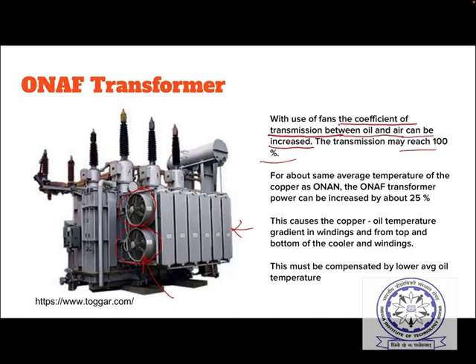For about the same average temperature of the copper as in the ONAN transformer, for example, the maximum temperature is one limitation and the average temperature is another one. So for the same average temperature as that of ONAN, the ONAF, the air forced transformer, power can be increased by about 25%. This is important. So an additional 25% extra power can be handled by the transformer by use of these fans.